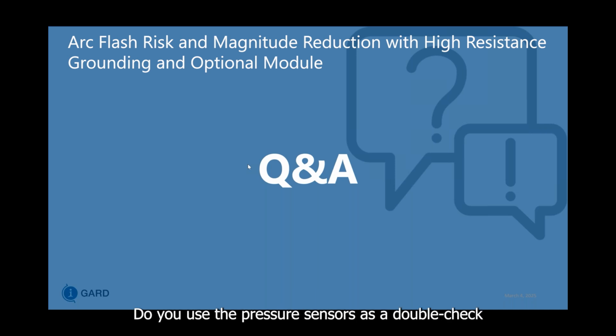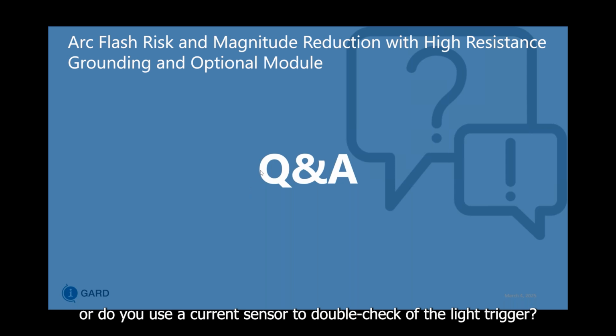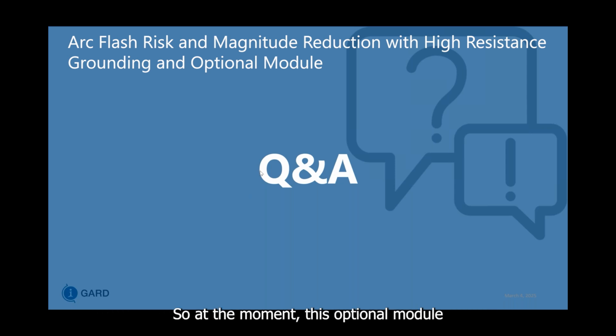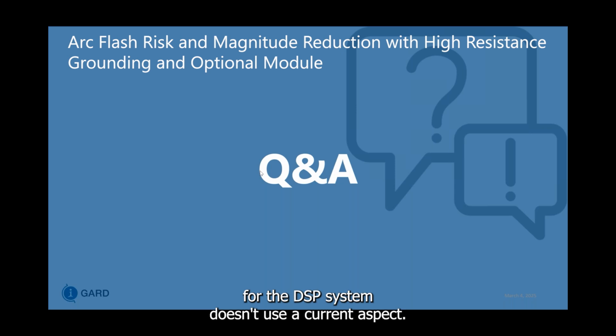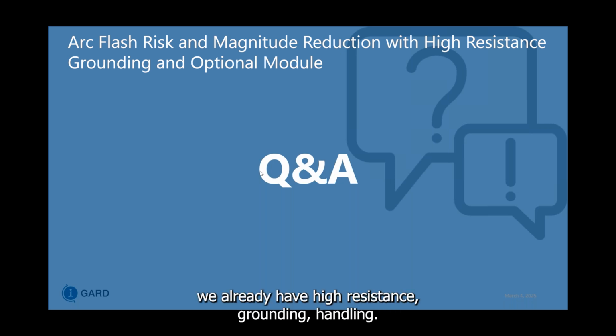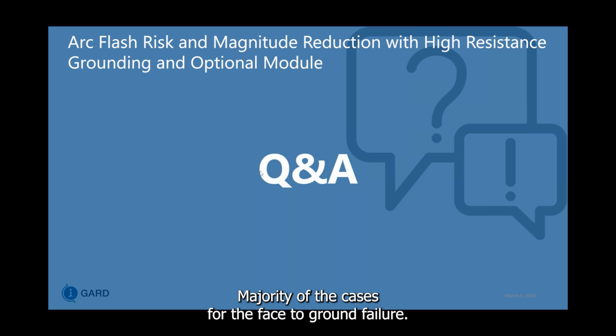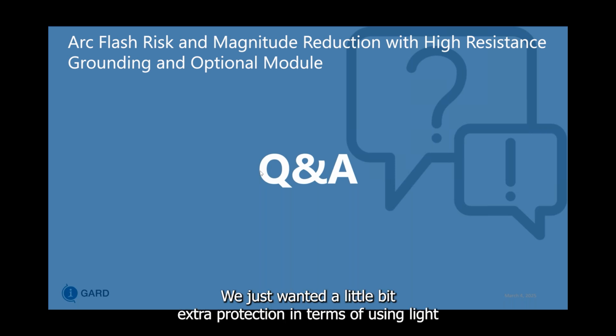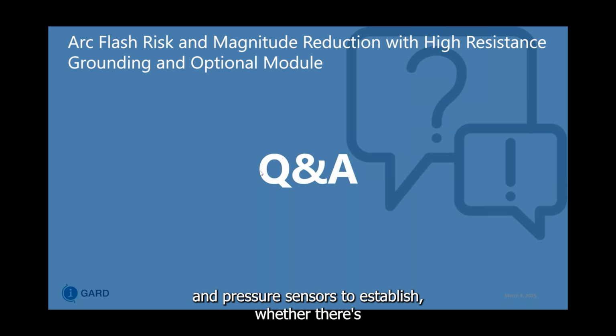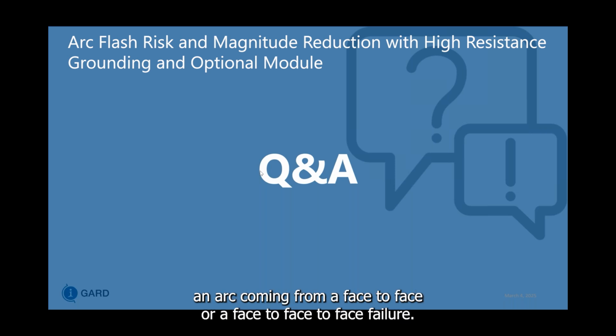Do you use pressure sensors as a double check, or do you use a current sensor to double check the light trigger? At the moment, this optional module for the DSP system doesn't use a current aspect. It only uses light or pressure. The reason is that we already have high resistance grounding handling the majority of the cases for phase to ground failure. We just wanted a little bit extra protection, using light and pressure sensors to establish whether there's an arc coming from a phase to phase or a phase to phase to phase failure.